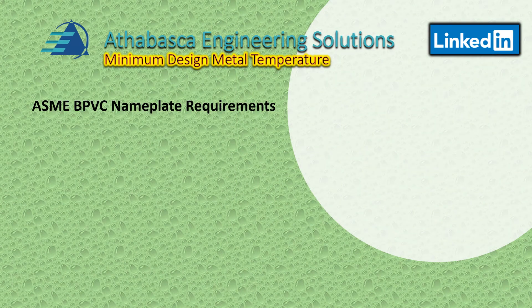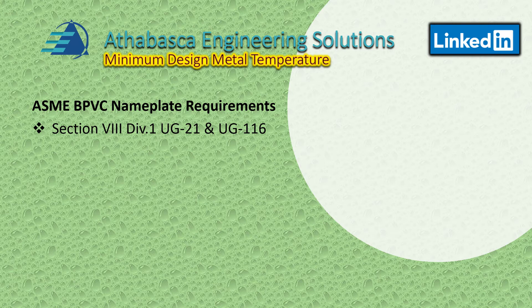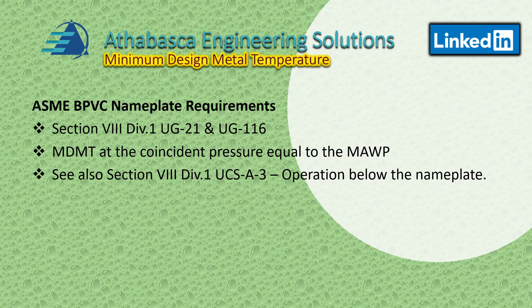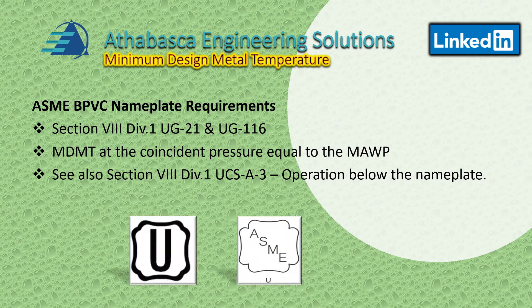Let's talk about ASME pressure vessel code nameplate requirements. In Section 8, Division 1, sections UG21 and UG116 have specific requirements. MDMT is required at the coincident pressure equal to the MAWP. You can also look at Section 8, Division 1, UCS-A3, which talks about operating below the nameplate values and procedures for that. These are the two types of stamps you would see on a nameplate, and it's a requirement to have the MDMT on nameplates as of 1987.